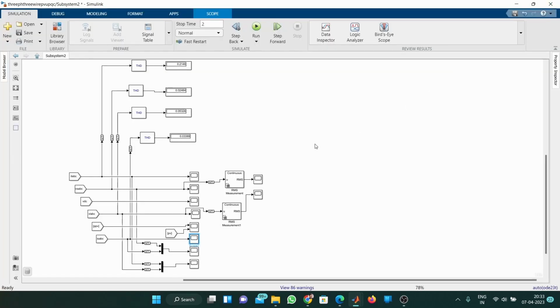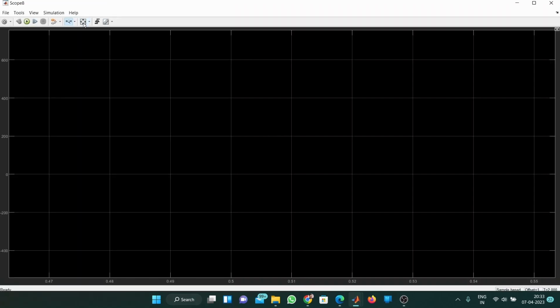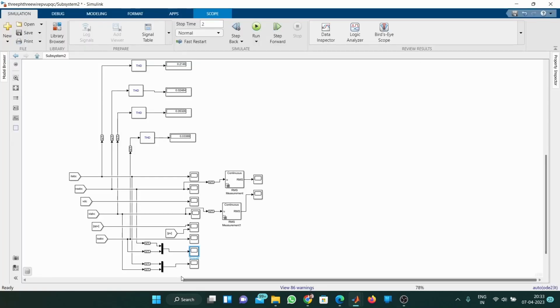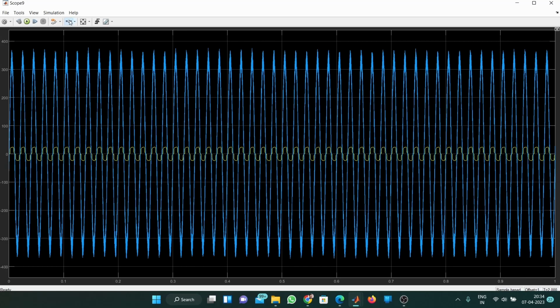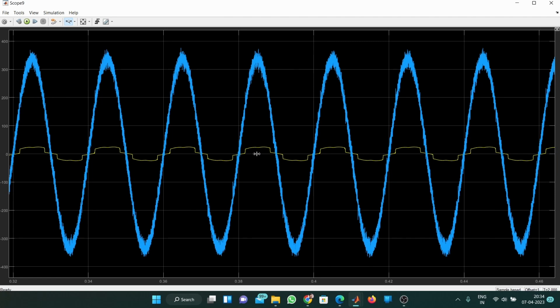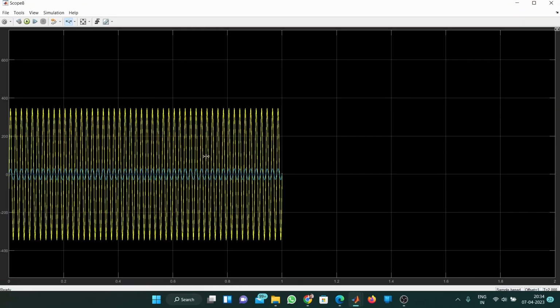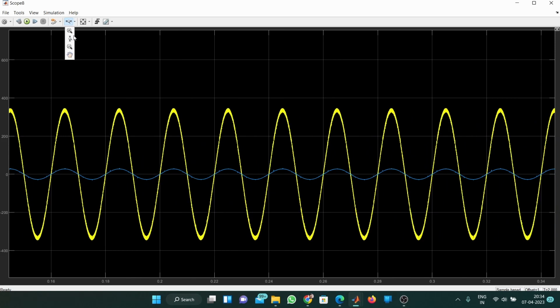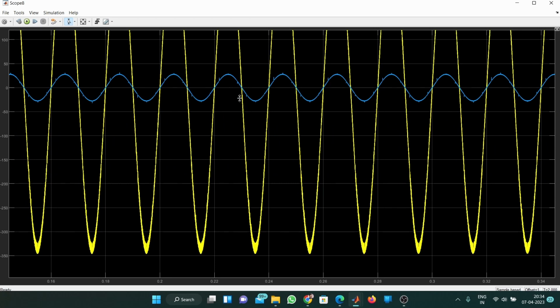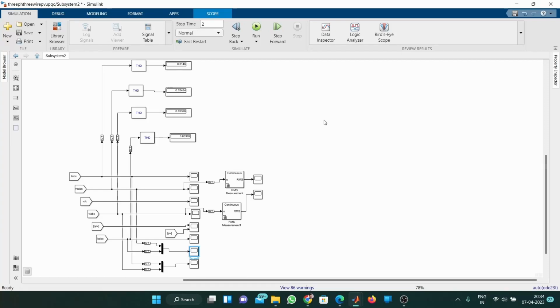Now we will move on to the second one, that is compensating the reactive power. If the load is taking reactive power, then the voltage and the current on the load side will not be in phase. I will show you the load side voltage and current. As you can see here, this is the voltage and current on the load side. It has harmonics and it is not perfectly in phase. Now I will show you the current and voltages on the source side. As you can see here, the voltage and the current are perfectly in phase, meaning there is a 0 degree phase shift. So the reactive power is being supplied by the DSTATCOM.